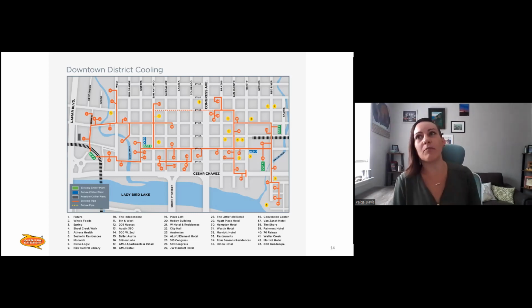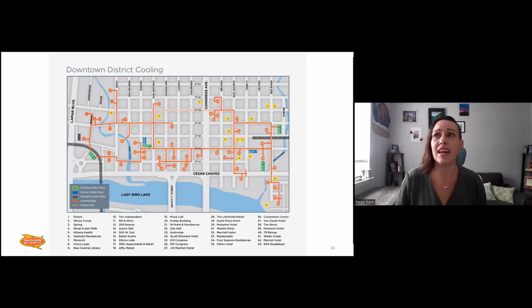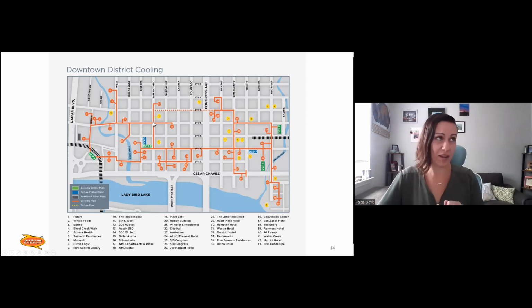We are going to be digging up and putting in some more chilled water lines. That's actually one of our big projects that we're working on now, is putting in that transmission line. As you can see, we don't have what you would really want, I guess—again, I'm not an engineer, but I'm told ideally you want to be able to have a loop in your distribution system. So we're putting in this line to help optimize the flow within the network and make sure that, like I said earlier, we're really maximizing what we can get out of all of the assets that we have in the ground.